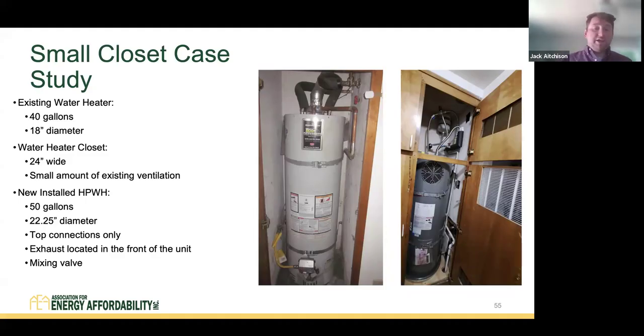One of the things that we did while we were speccing out this project was making sure that we were selecting a heat pump water heater that had water connections on the top. Sometimes they have them on the side. We have a very, very small amount of clearance on either side of this water heater, so we had to have top connections. We also selected a water heater that had the exhaust in a place that we could orient it so that it faces the louver here so that it can get proper ventilation.